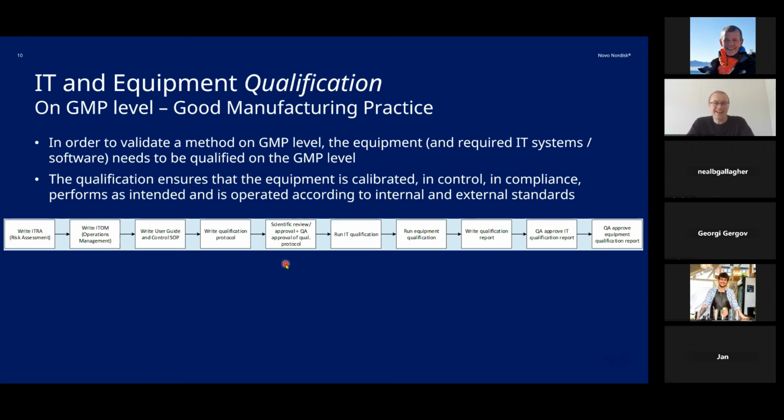we have it locked. I mean, when we have, let's say, a validated pharmaceutical method, that goes hand in hand with a validated method that we use to generate the validated pharmaceutical settings, and that method is considered to be locked.